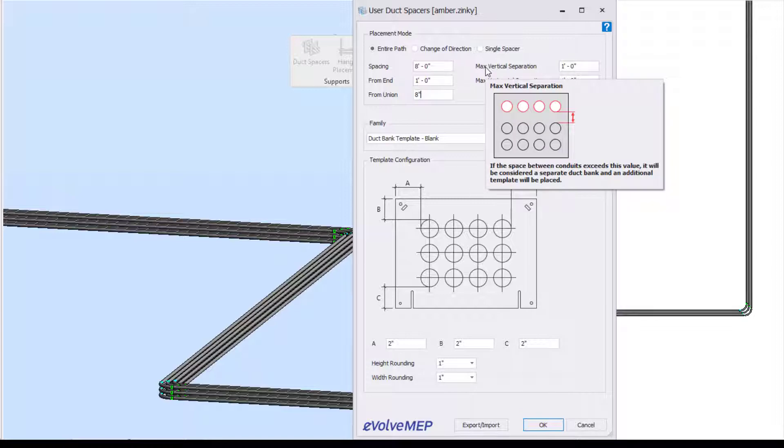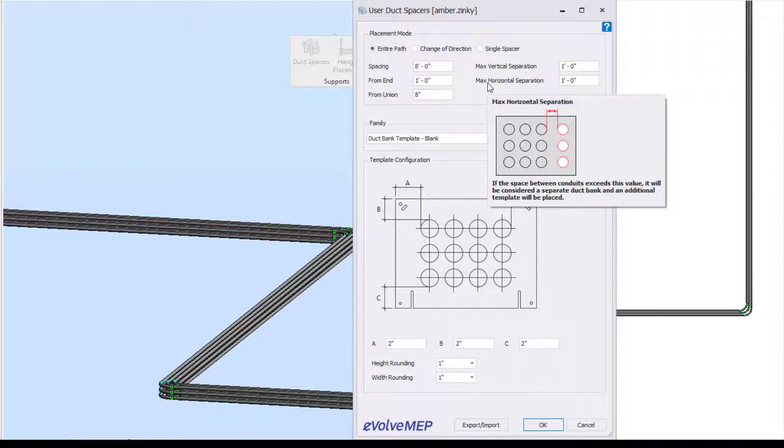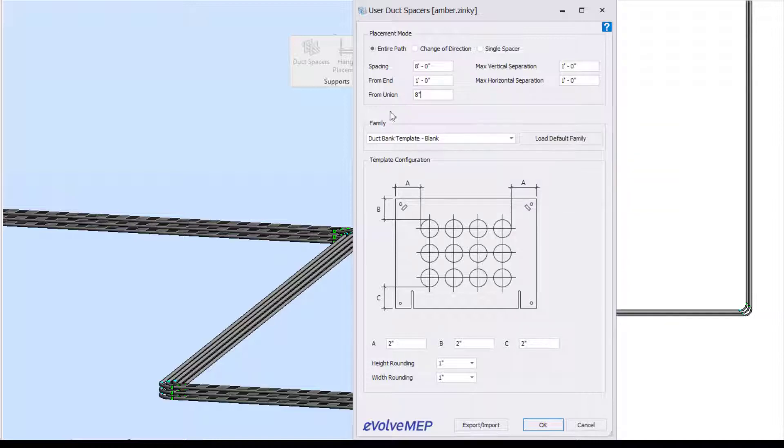And then we'll have our maximal vertical and horizontal separation. You can see from the pictures it's telling you what this means - that if the spacing between the conduits exceeds this value, then it will be considered a separate duct bank.